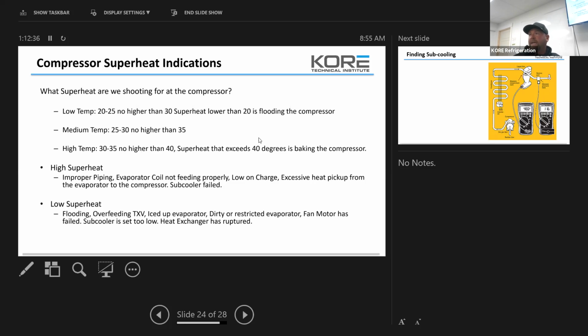So what is happening anytime you have high superheat is you're either not condensing or you're picking up so much heat that you don't have enough heat pickup property to absorb the heat in the compressor. So what happens is the compressor gets hotter and hotter because we're not absorbing the heat through the cycles, and then it overheats the compressor. That's why it's important to watch superheat.